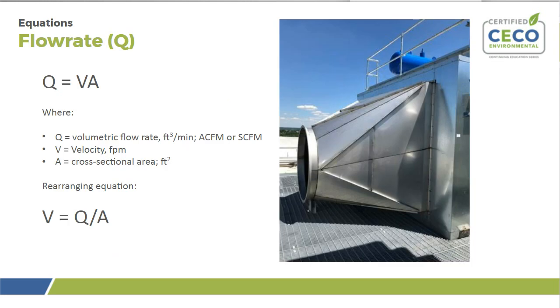The second important equation is Q equals VA, where Q is the volumetric flow rate in feet cubed per minute. V is our velocity, and A is the cross-sectional area of the duct. Cross-sectional area is the diameter of the duct where the velocity pressure is measured. Flow rate should always be stated in actual cubic feet per minute or standard cubic feet per minute to allow correct interpretation of the flow rate. Determining flow rate from measuring the velocity pressure and knowing the duct cross-sectional area is a great troubleshooting tool to determine if the flow rate of an existing system is what was originally designed and expected. Flow rate and its effect on other ventilation components must be considered.